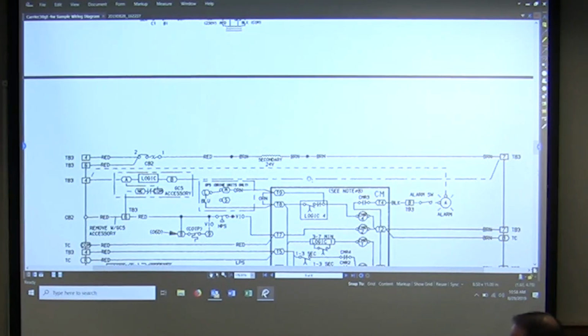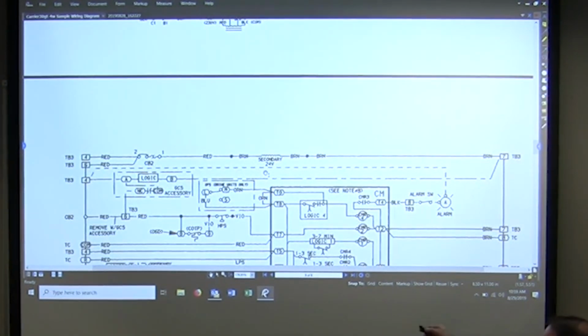Anybody else think we could do it differently? Would we want to go 1 and 7? One's coming off a fuse. You could do one, yeah, because 1 and 7 is on the hot side. You can go 1 and 2 and have it close on alarm if the fuse blows. Yeah, you want to check and make sure your fuses are good. So there's a couple ways we can do this. If I were to tie 1 and 7 to my relay coil, what happens if this fuse or my circuit breaker opens? You get a feedback to your system telling you that you've got no power. You don't, because 1 is still hot; this is always energized.